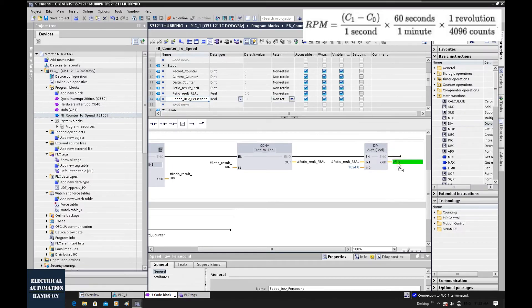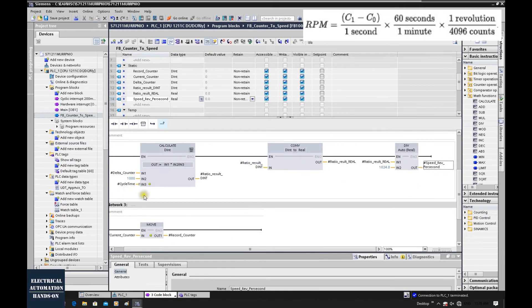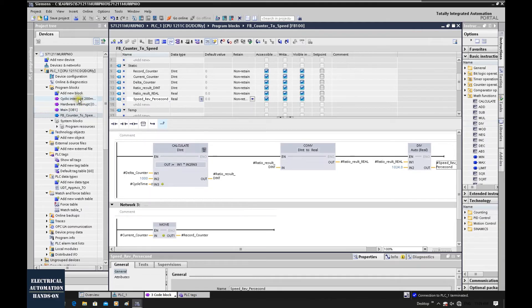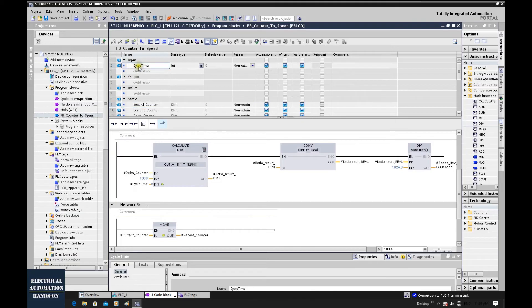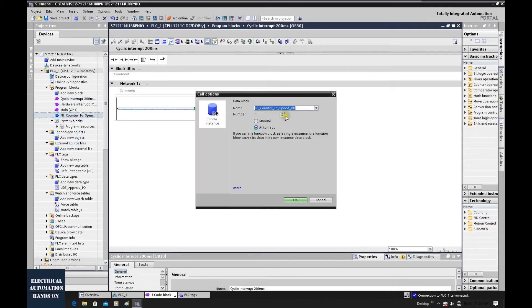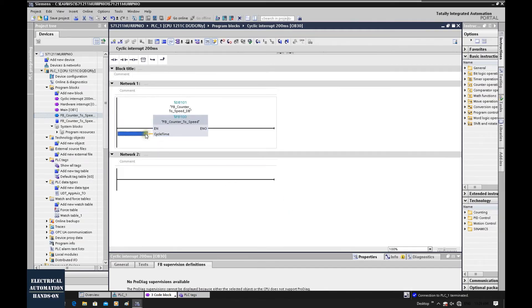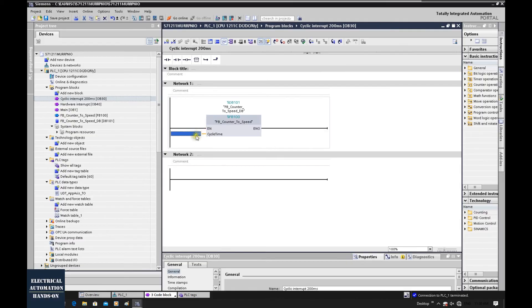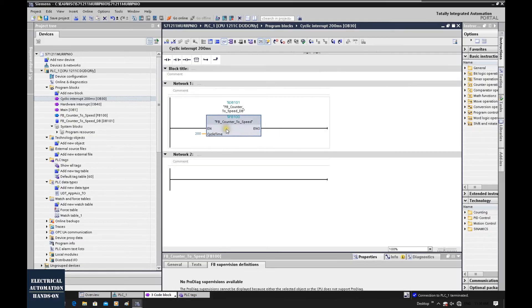Drag the speed result to the output. This completes the entire equation to convert the counter to speed in revolutions per second. Now we go to OB30 and call FB100, which generates instance DB101. We type in 200 for the Cyclic_Time parameter, because OB30 is set to 200ms. If in the future you use a 500ms OB, simply type 500 as the parameter — very flexible. Now we download the program.